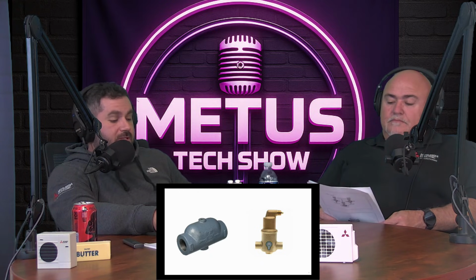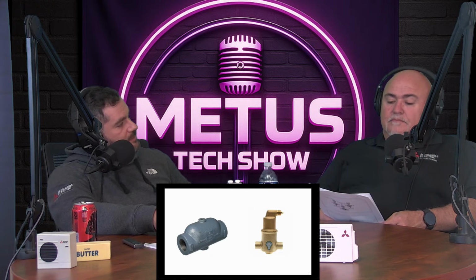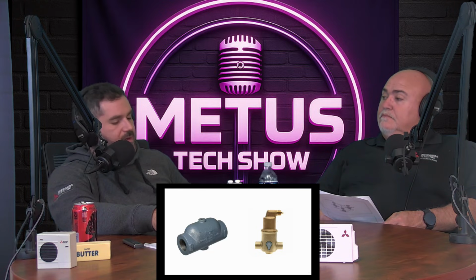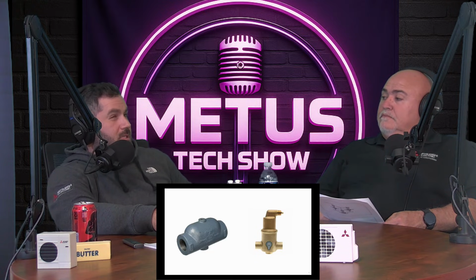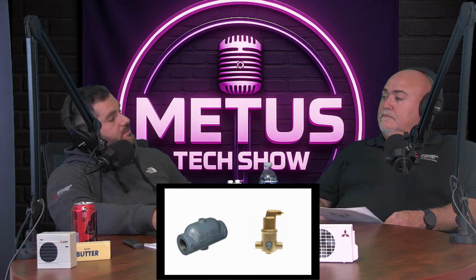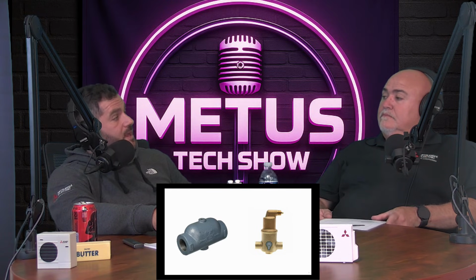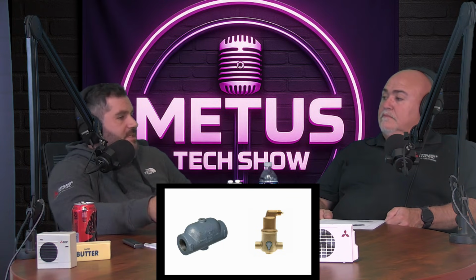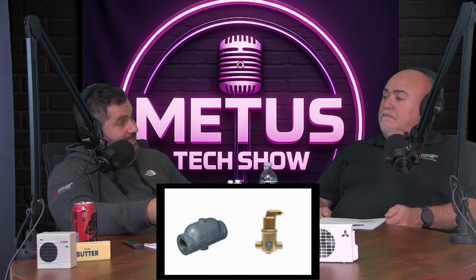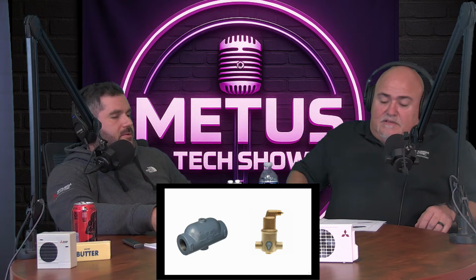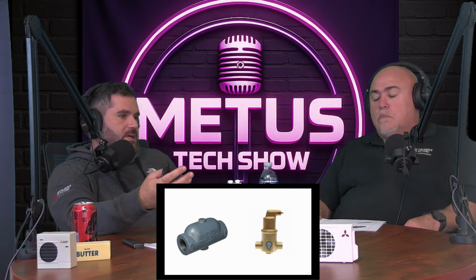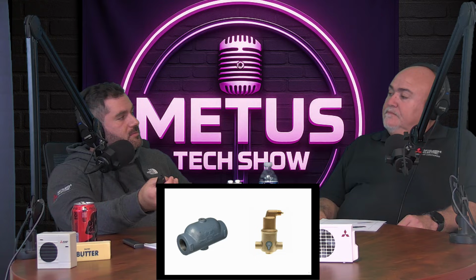So these are required. You're not going to be able to get away with piping a system without some sort of air elimination, because even if you purge a system perfectly and you have no air in the system based on your purging practice, when that water heats up, it will release microscopic, they call it saturated oxygen, that exists in the water. Microbubbles. Microbubbles, yeah. So when that water does heat up, it's going to release some small amount of oxygen.